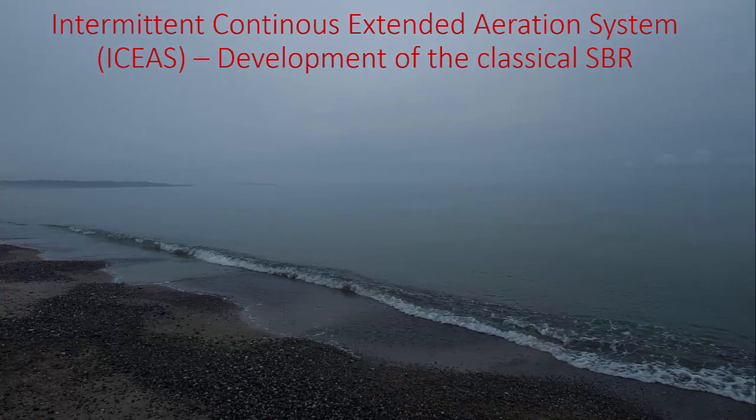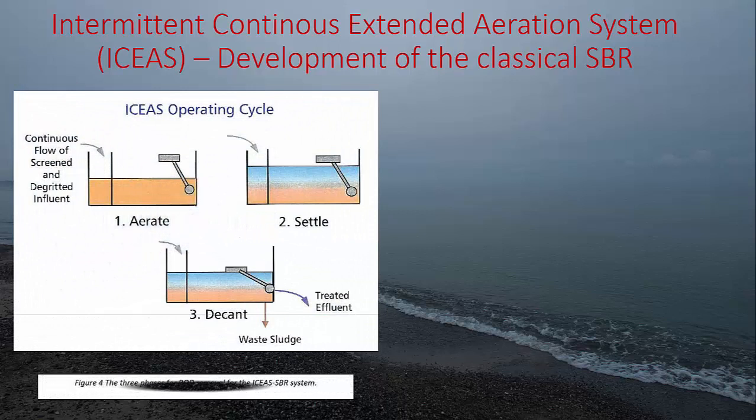In the late 20th century, there was development of the SBR into the intermittent continuous extended aeration system, or short ICEAS. The ICEAS system has a continuous inflow, which means that during the aeration phase or reaction phase, you have an inflow to the tank. You go to the second phase, the sedimentation phase. You still have an inflow to the tank, and to a third phase where you decant, you still have an inflow to the tank. And also during the decant phase, you waste the sludge or pump out the excess sludge.